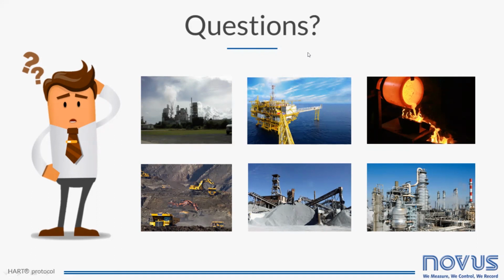There is one more. Should I only use a 250 ohms resistor? Not necessary. The minimum impedance from the HART device is 250 ohms, and the maximum is 1,208 ohms for a power range between 30.8 and 36 volts. Another question, how should the resistor be connected to the current loop? The resistor should be connected in series on the loop, regardless of its polarity or position in the loop.